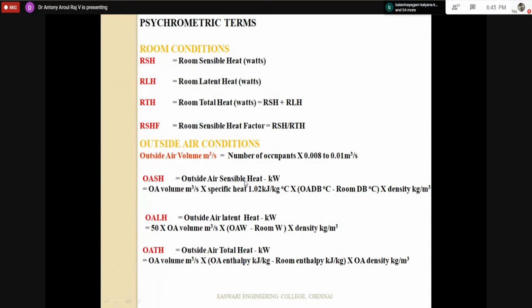Then what is the outdoor air latent component? I am going to take the same quantity of air, dictated by the ventilation standards or by the number of occupants. Now, in summer air conditioning, the outdoor air has higher humidity and the indoor air has low humidity. You want to maintain 50% RH, so whatever the corresponding specific humidity is, that will be the room humidity.